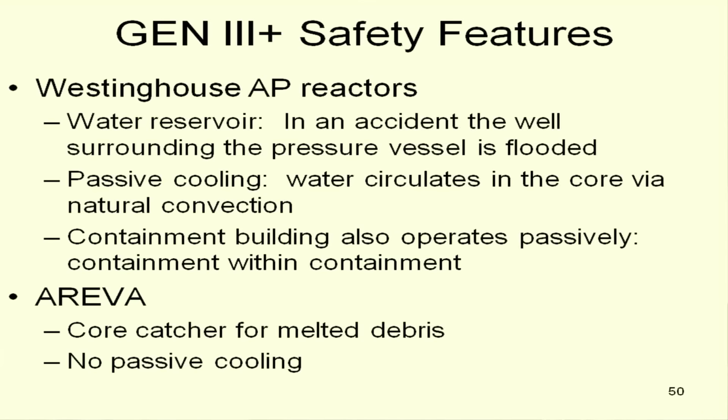The Generation 3 Plus, these are the more advanced ones that are just coming on. For the PWRs, in an accident, the well surrounding the pressure vessel is flooded, whereas during normal operation, it is not. But there's the capability to flood that. They designed it so as to get passive cooling in the core. They don't need to actively circulate it with pumps, although they do need special provisions for heat removal there, because even if it circulates itself, it's still warming up.